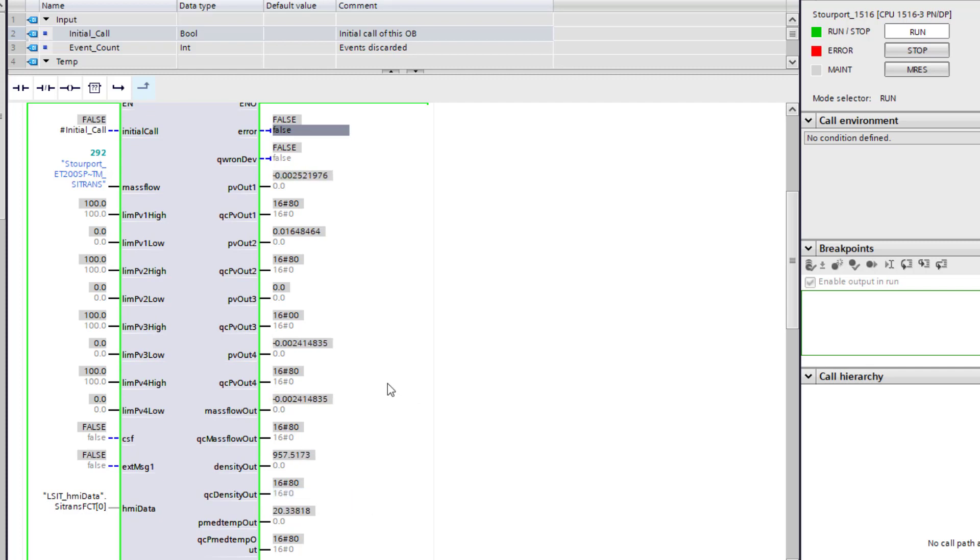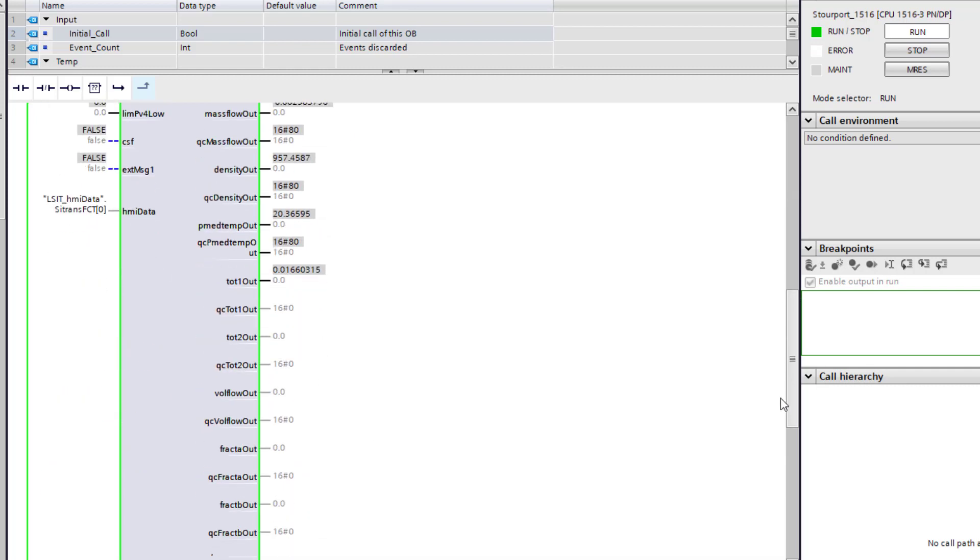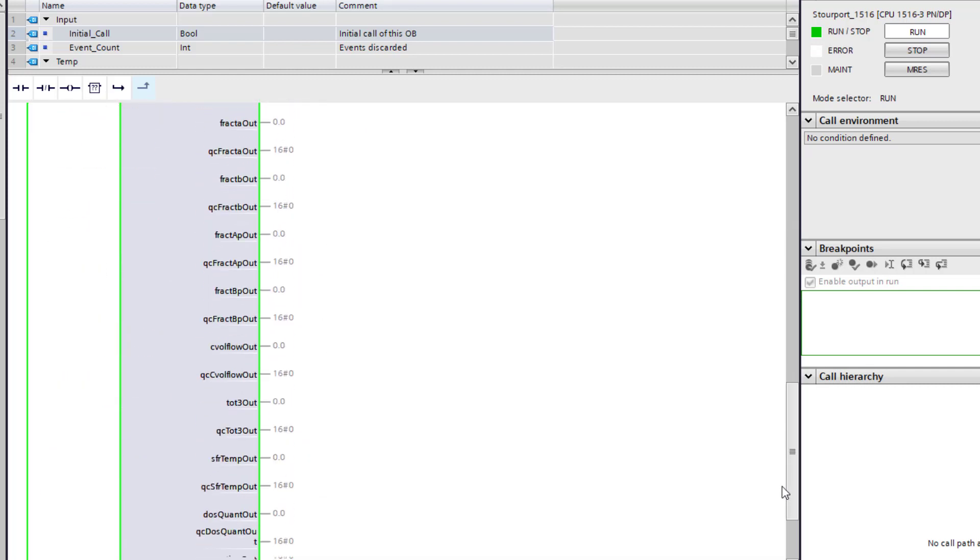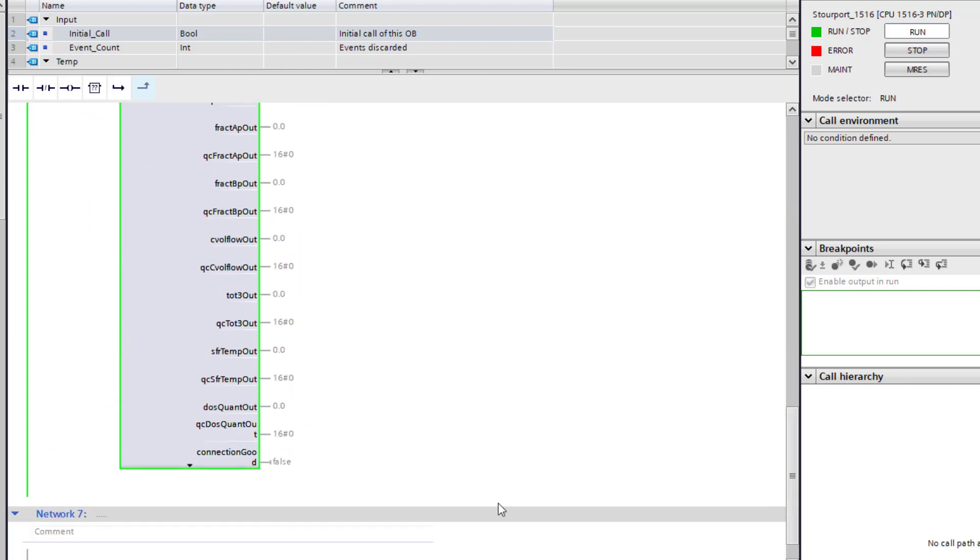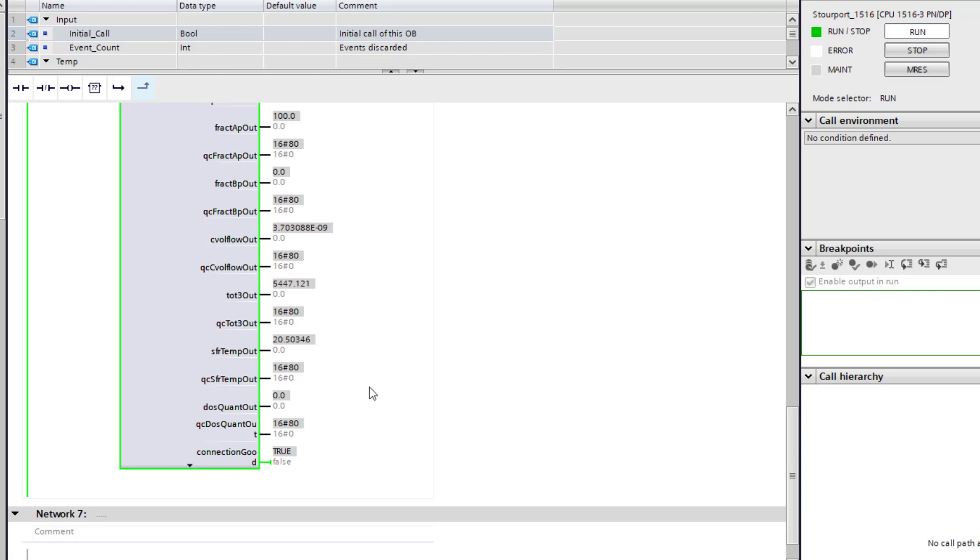And there you can see the status. Hex80. That conforms with the Profibus status and the HART status. And then at the bottom you will see this connection good. That should be true. So we want to see a lot of these Hex80s. We want to see the temperature OK. And once you have got that, you have actually managed to bring the block into your project. And you could just leave it like that if you wanted to. And take those values off manually to other parts of your process.